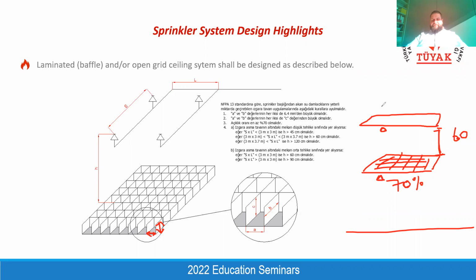That's why you need to check the physical conditions of your ceiling, and you need to check the openness, and also you need to decide the levels of the suspended ceiling so that the lower level sprinkler can be omitted and you can find a view that is required from the architect's point of view. Otherwise, you will have a sprinkler beneath the open grid ceiling, and it does not look really good when you compare it with alternative decorative objects.